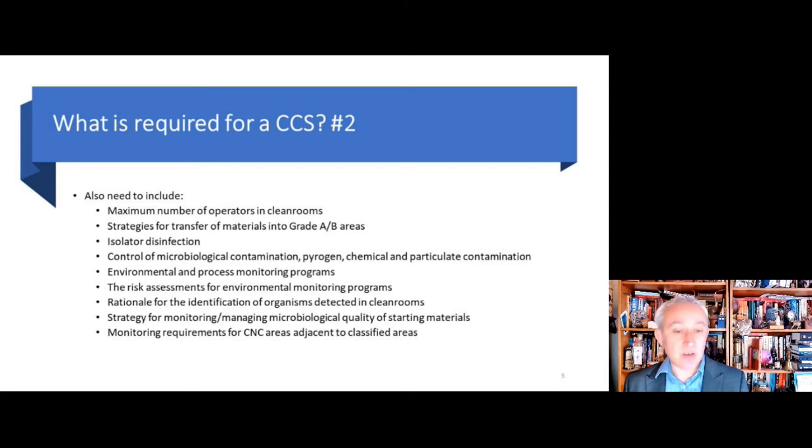There are some other elements as well. We need to give consideration to how many people are going to be allowed in a clean room at any one time, because they're the key influencers of particulate control. Risk evaluation and mitigation strategies for the transfer of materials into the grade B or grade A area. Transfer disinfection is one of the fundamental weaknesses in many facilities. Isolator disinfection, control of contamination not just for microbial but also for pyrogen and particulate contamination and potentially chemical.